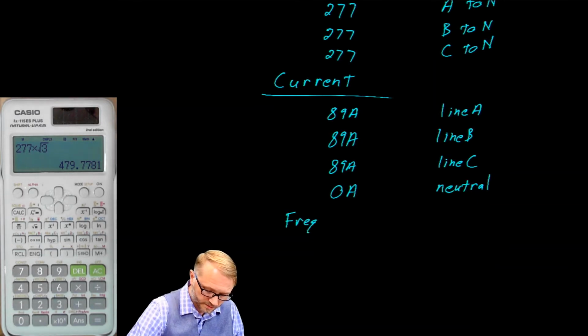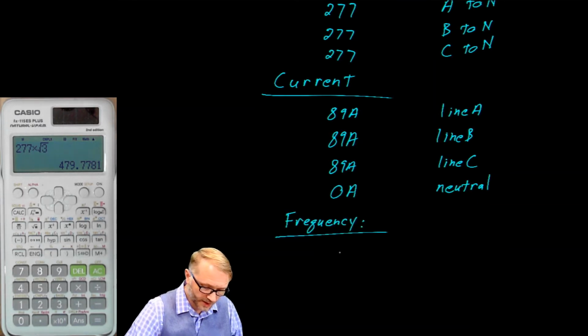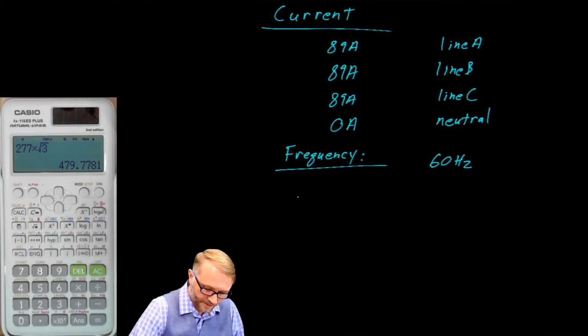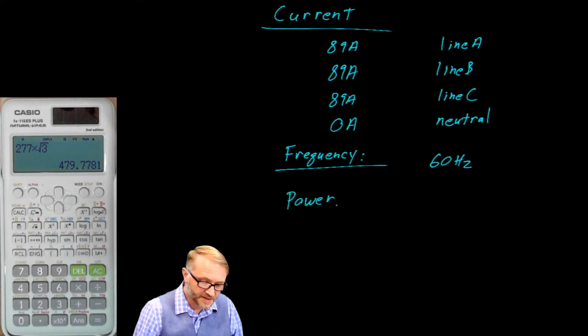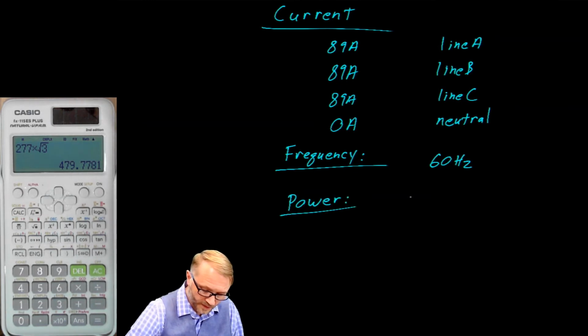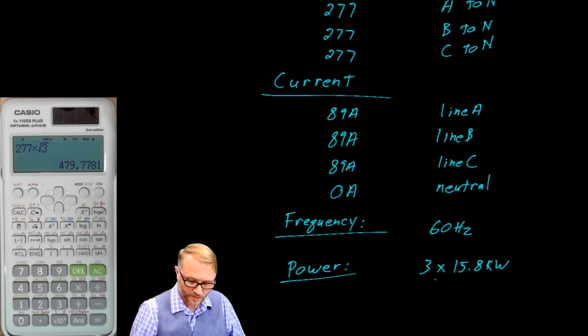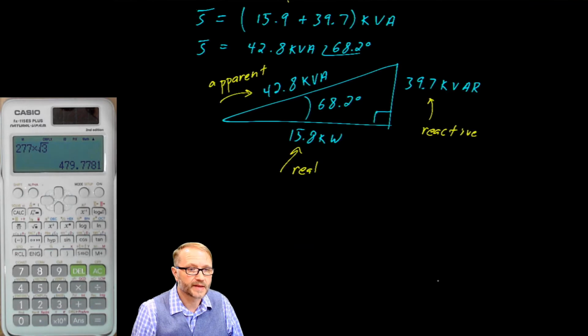Frequency, that should equal 60 hertz. Power, in this case real power, should be 3 times 15.8 kW. You should ask where this 3 came from, and the argument goes something like this.